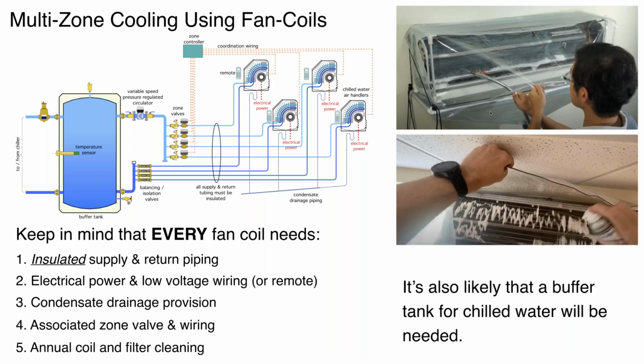Okay, and also, depending on the heat pump, you might have to use a buffer tank, simply because these units might be in the range of 3/4, 1, maybe 1.5 tons capacity at the most. If you've got a single speed 4-ton heat pump, you know, you're going to get into a short cycling problem without a buffer tank. Now, the inverter heat pumps, different story to some extent, although again, extensive zoning could still require a small buffer tank.